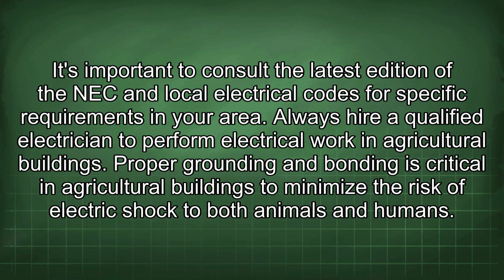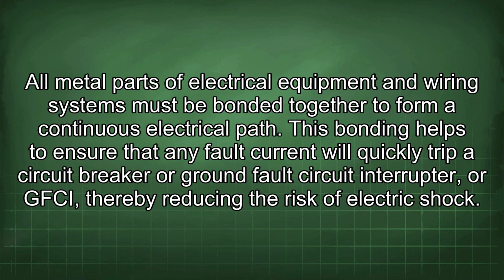Proper grounding and bonding is critical in agricultural buildings to minimize the risk of electric shock to both animals and humans. All metal parts of electrical equipment and wiring systems must be bonded together to form a continuous electrical path. This bonding helps to ensure that any fault current will quickly trip a circuit breaker or ground fault circuit interrupter, or GFCI, thereby reducing the risk of electric shock.